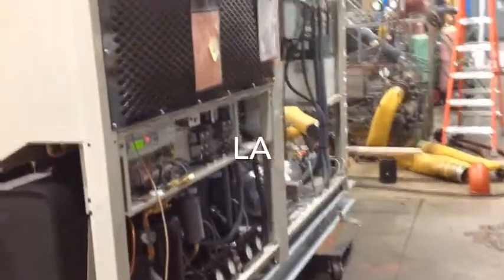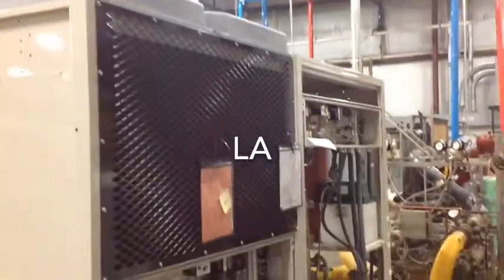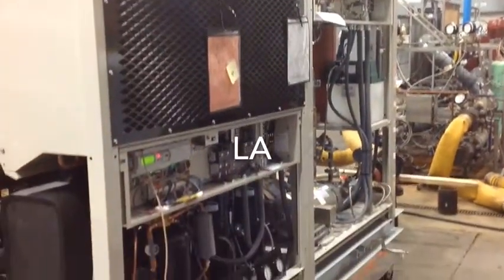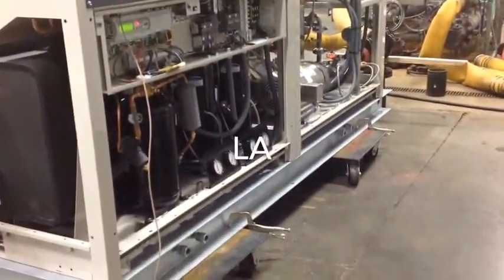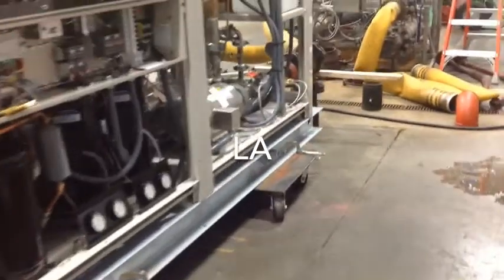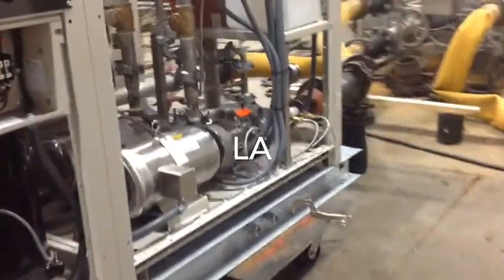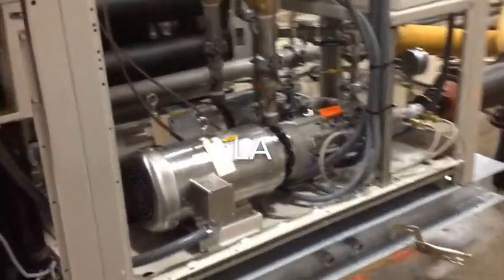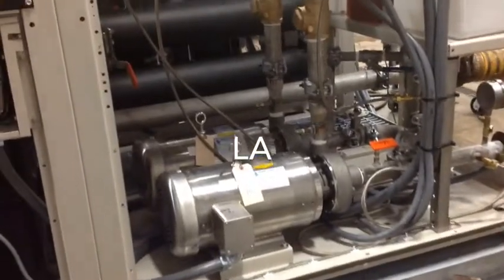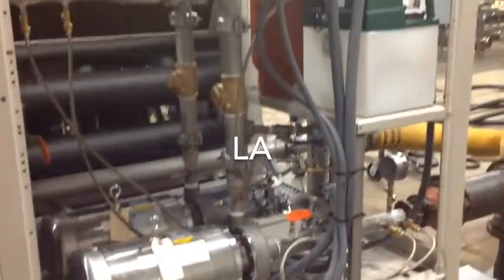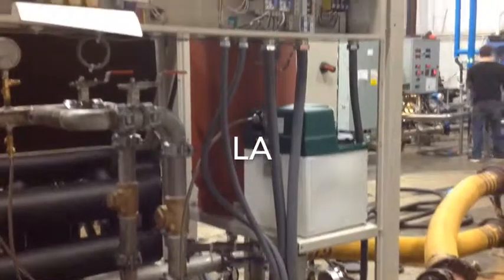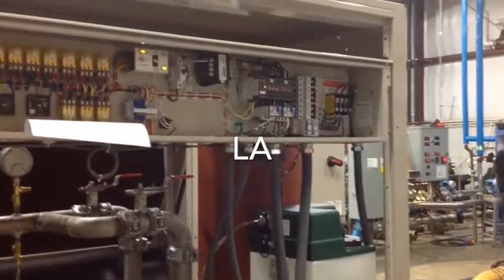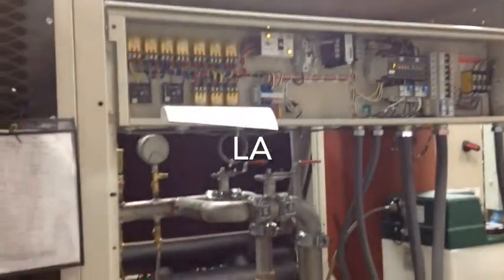Now we're swinging around and you'll see the master module, panning up to see the condenser coil section, and then we'll come around and see the pumps. The chiller, as submitted, has independent circuits in each of the 3 mechanical modules. Here you see the 2 stainless steel chilled water pumps, the glycol mini feeder, and the expansion tank, standard pump control cabinet.